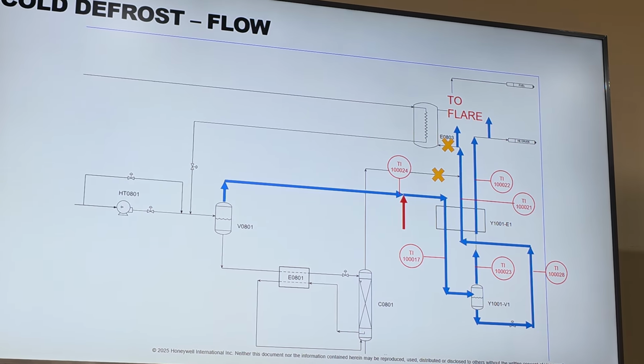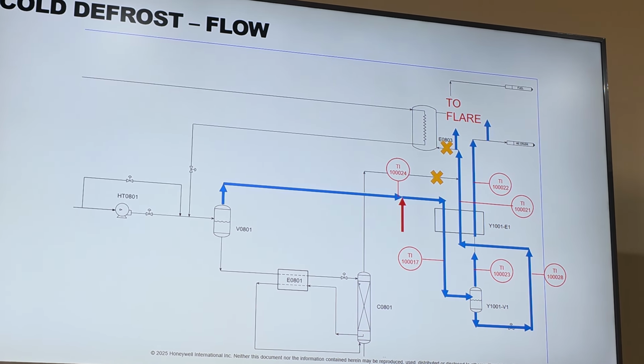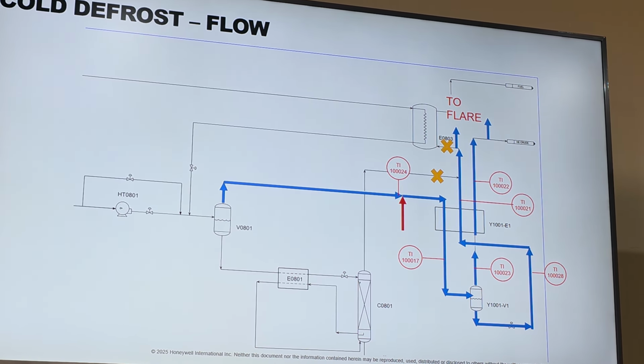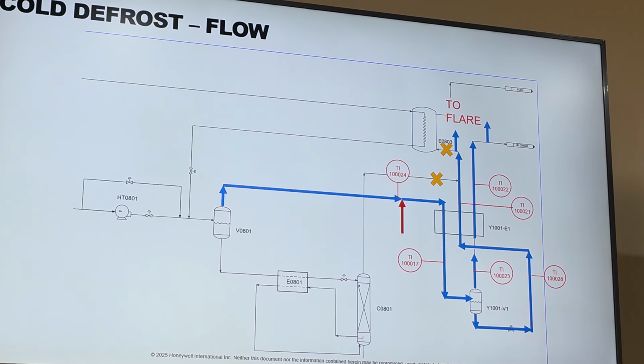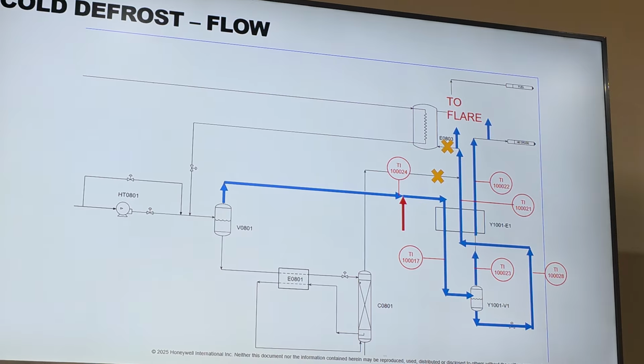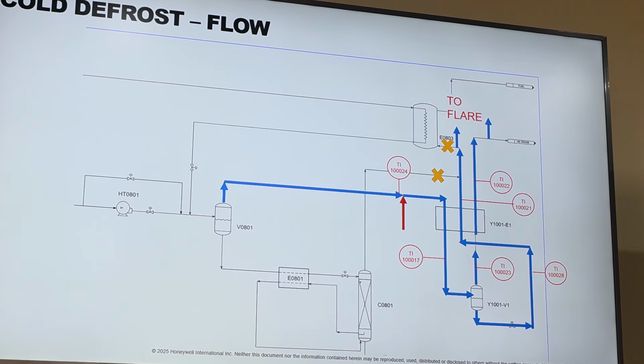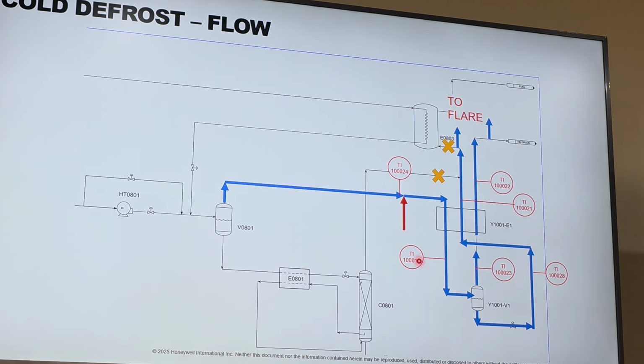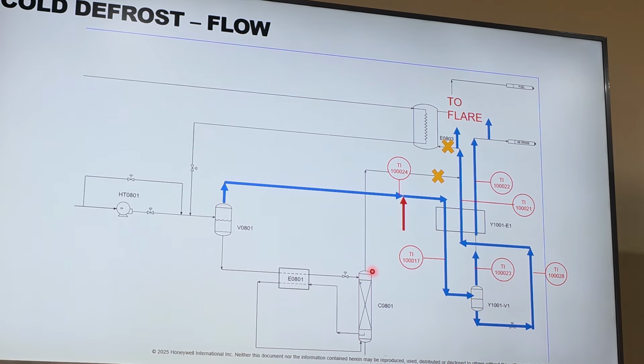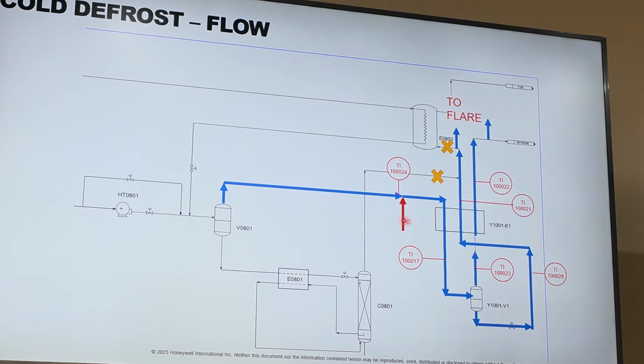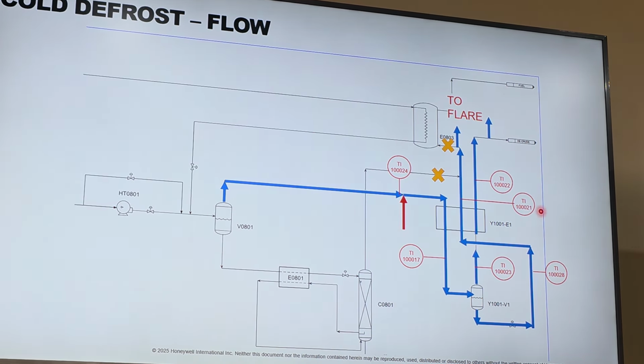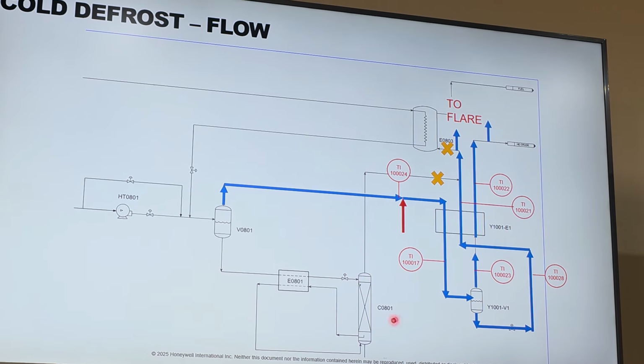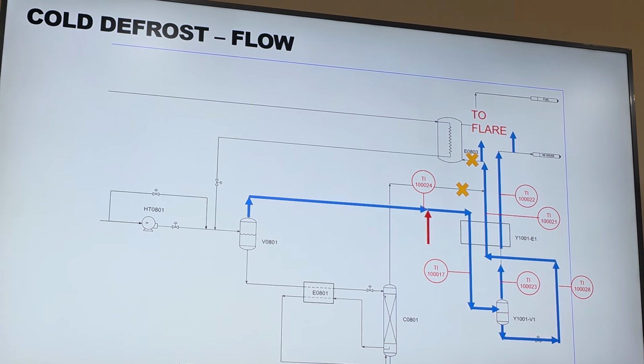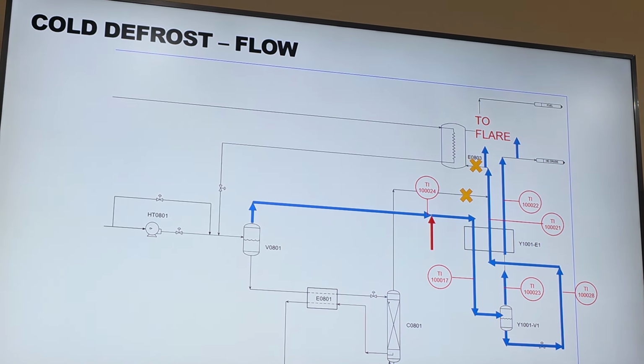There's only one control. The nice thing about the helium recovery system, there's one control valve. It's the level valve on the drum. It's the only thing you can do. You can either open it or close it. Pretty straightforward. Okay? So that's how you do a cold defrost. And then, of course, once you get up to ambient, you can isolate it and you're just going to use defrost gas.